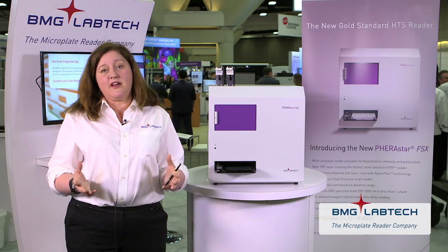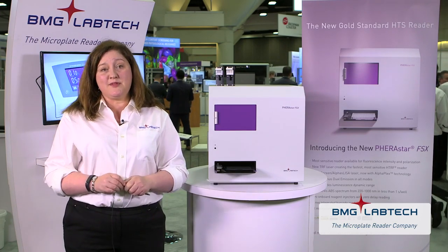For alpha technology, we see generalized improvements based on the optical changes employed — lower background and even better crosstalk reduction over the great performance we already see with the PHERAstar FS. I want to highlight the addition of simultaneous dual emission for this read technology, which has really been driven by the change in assay technology. Customers can now duplex AlphaScreen in the same well with AlphaPlex technology from Perkin Elmer — two sets of alpha beads, two different emissions. With the FSx, you can read those simultaneously. Users familiar with AlphaScreen will know that when you activate the beads you see a depletion in signal, so sequentially reading these assays might impair your second read. Simultaneous dual emission gets the best readout from both sets of beads in the fastest read time — a fantastic feature enabling the future of assay development.